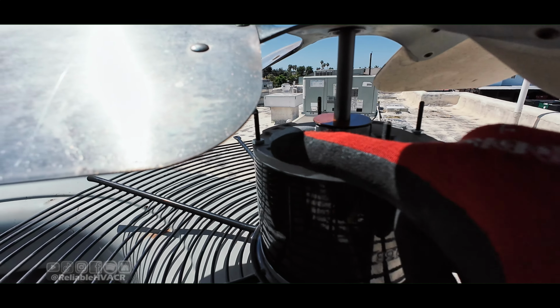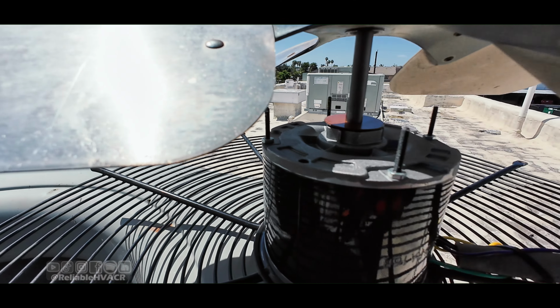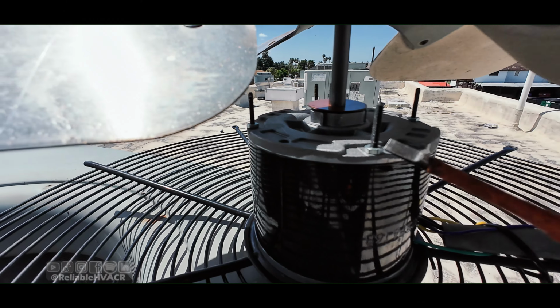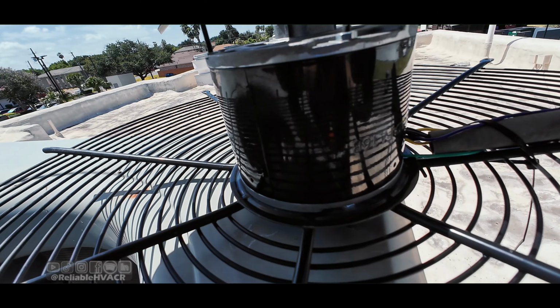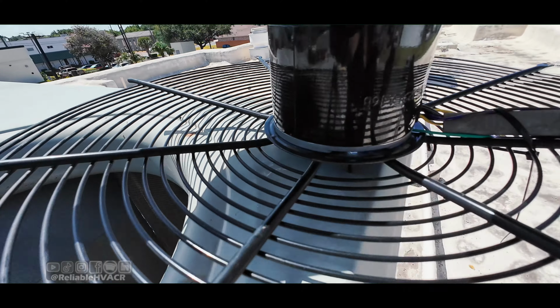It's upside down. That's just a drain plug. If any water gets in the motor, it comes out through here. Do not remove the one that's on the top of the motor. So if it was facing like you see it right now, you would leave that one on, remove the bottom. If we're turning it around like today, removing this one, keeping the one on that side.